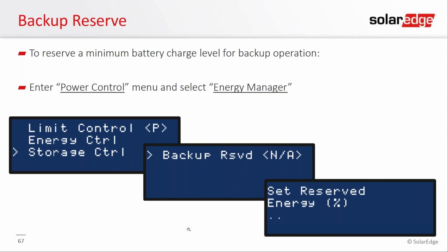All right. In backup mode, can you run a well pump? That's also the biggest one. So a well pump is a 3 horsepower pump typically, and that is just a huge load, and it has a lot of inrush current. And you saw that our maximum inrush is 6.6 kilowatts. If you do the math, 6.6 kilowatts divided by 240 is going to be like 27 amps. So we're not going to be able to do anything quite that large. A lot of people said, oh, I've got this variable speed well pump that may not have as much inrush. I don't know. That's going to be up for you guys to decide. In general, I'm going to say no, can't do well pumps, but there's an asterisk there and a heavy sigh.